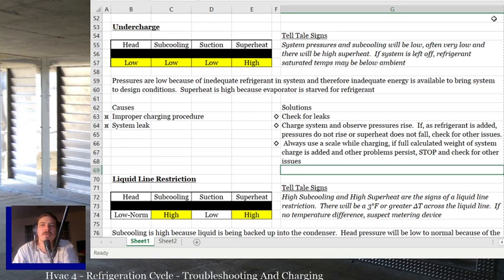So if that system says it holds 5 pounds of refrigerant and you add 5 pounds and this stuff's not changing, it wasn't an undercharge. Stop. Go back, pull out what you put in, recover it so that you can weigh it back in and calculate it with the line set and put in a proper system charge, and then figure out where your diagnosis went wrong. But it's always a good habit, if you think there's an undercharge, pull out your scale while you're weighing it in and look for things starting to get normal. If things aren't starting to get normal as you weigh it in, you just misdiagnosed it and you need to figure out what's going on.